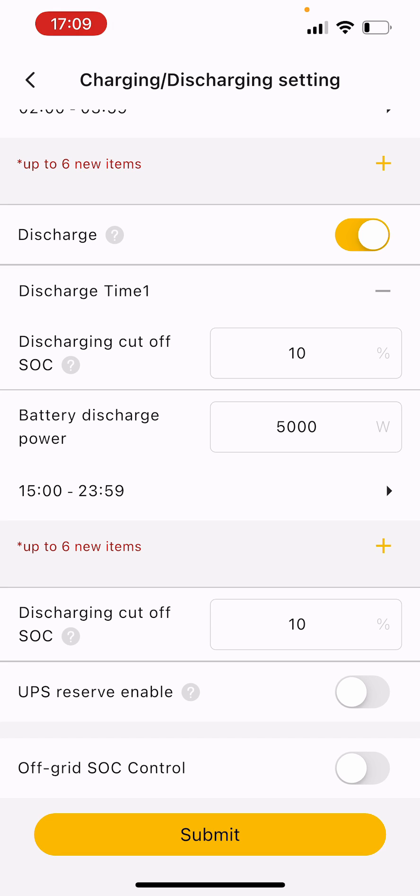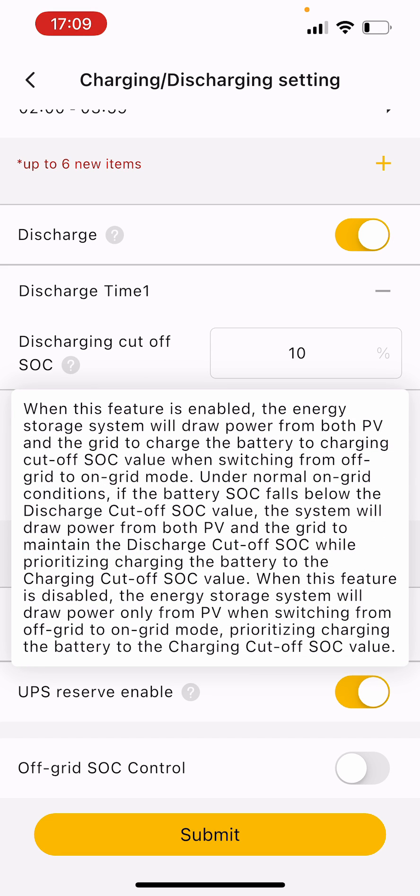UPS reserve is backup reserve. If you lose the grid, we'll have power outages. It's just how the battery will work if it goes below that cutoff. If you lose grid power and the battery discharge is below 10%, when you get the grid power back, the battery will charge by the grid and PV to get it to that 10% straight away.